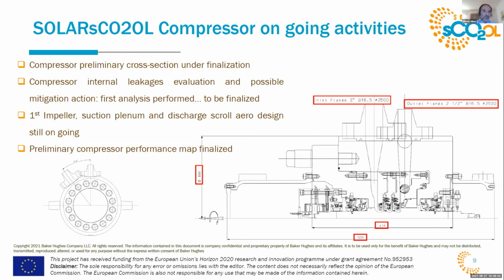At this stage, we are also carefully evaluating the internal leakages of the compressor, because in correlation with the small dimension of this machine, leakages that are less important for our standard compressors become very crucial here, as they can significantly affect the efficiency of the machine. This is under deep evaluation, and we are trying to figure out what mitigation actions can be carried out to reduce it. The expected end of this analysis is by the final detailed design of the compressor, due by almost June next year.